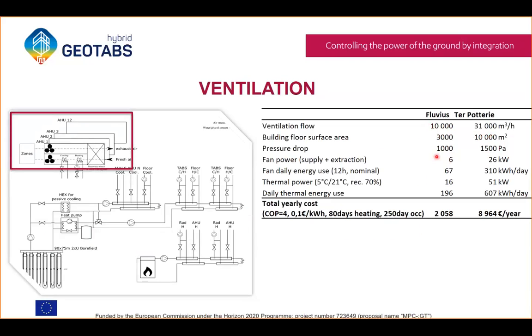If we consider typical pressure drops in the ventilation unit and also in the duct system behind it, and assume that the fans are running at nominal power for 12 hours, we already have about 70 kilowatt hours per day for Fluvius and about 310 for Ter Potterie. Additionally, if it's cold outside, the air will need to be heated up. Assuming that the comfort within the building is 21 degrees and that we have a heat recovery of 70%, we get an additional 200 to 600 kilowatt hours per day. So if we have a ventilation system working at nominal condition for 250 days per year, with about 80 days of heating, electricity at 10 cents, and all the heat produced by a heat pump, we get numbers as high as 2,000 up to 9,000 euros per year.